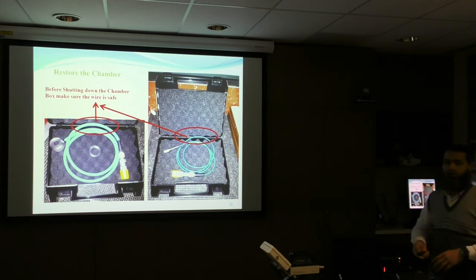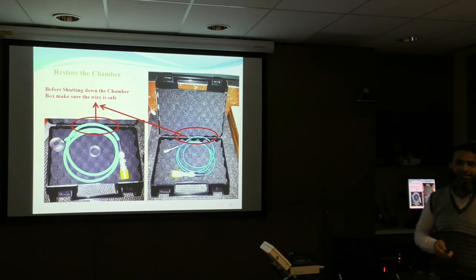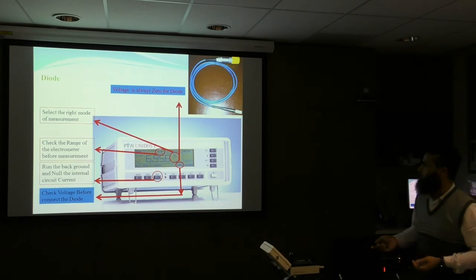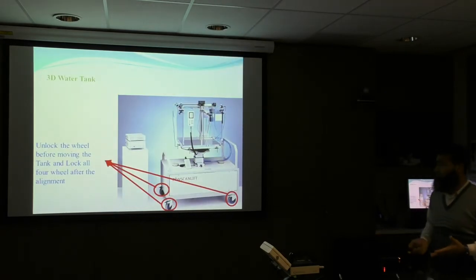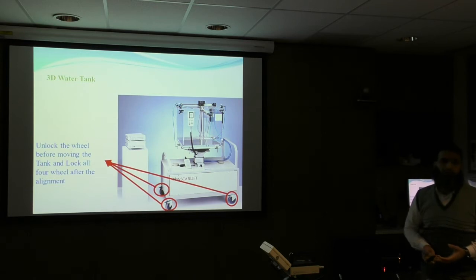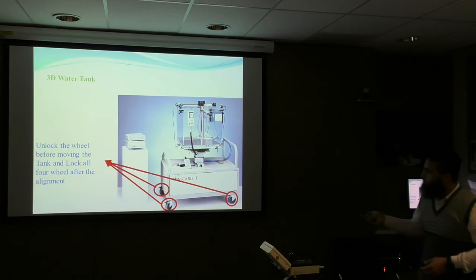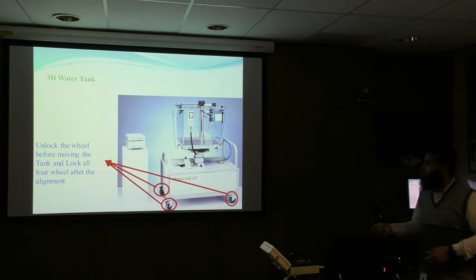Just be very careful. This gives you an idea of what not to do when you go to the clinics. The voltage should always be 0 when you are using a diode, as I've already explained. When you use the water tank - which you don't use routinely, but whenever you're doing commissioning or whenever you have a major breakdown on your machine - you normally use it.